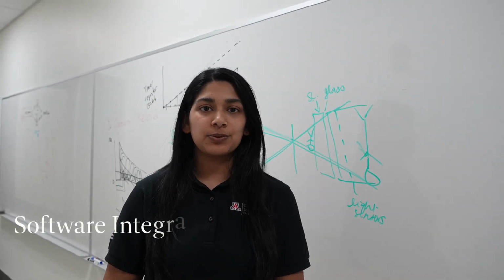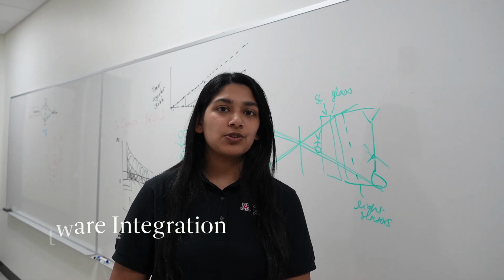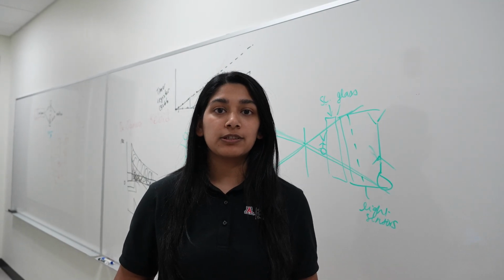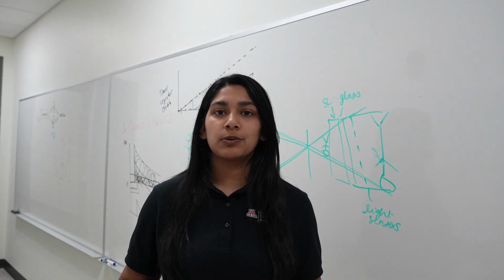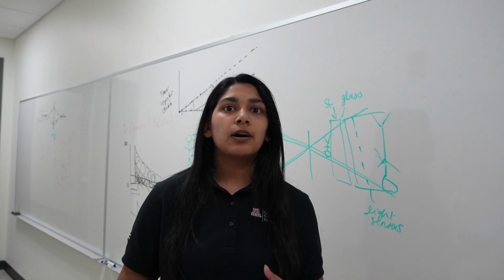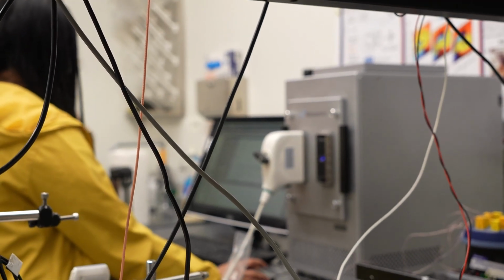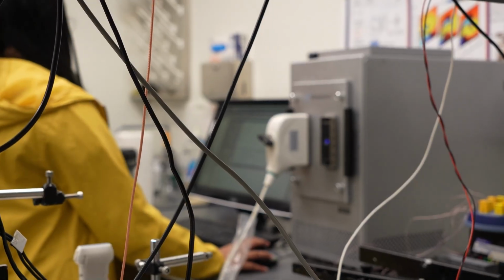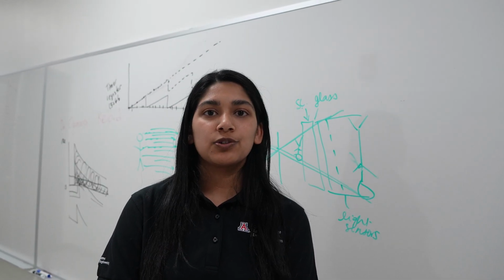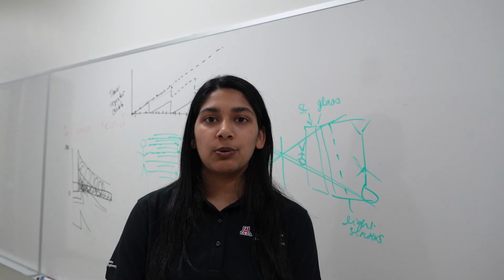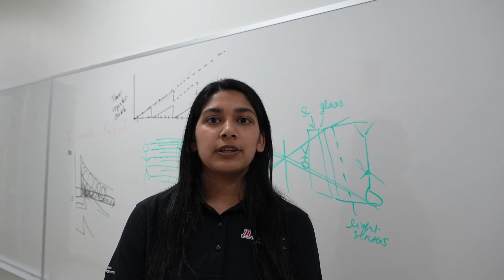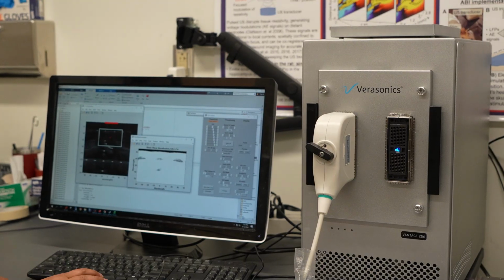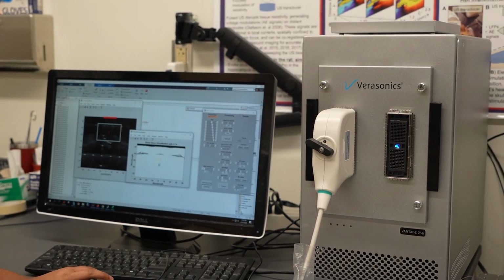One of the biggest issues that we faced was software integration. Initially, we had the motor script and the imaging script as two separate things, and even with the imaging script, there were two separate variations of that. To fix this issue, we had to integrate the motor logic into the scanning logic. We implemented this motor control logic in both the B-mode scan and the shear-wave imaging scan, and it also allows the users to adjust the scan distance and the step size for both these modes.